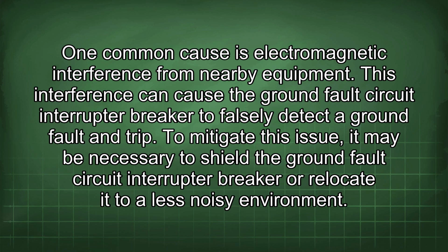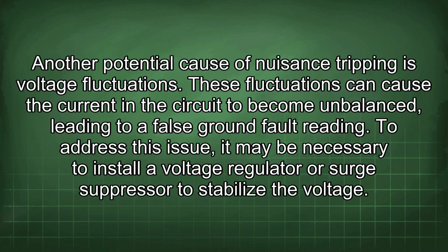Another potential cause of nuisance tripping is voltage fluctuations. These fluctuations can cause the current in the circuit to become unbalanced, leading to false ground fault readings. To address this issue, it may be necessary to install a voltage regulator or surge suppressor to stabilize the voltage.